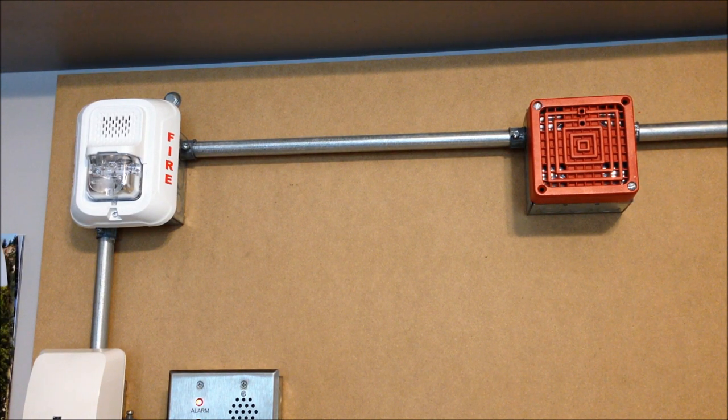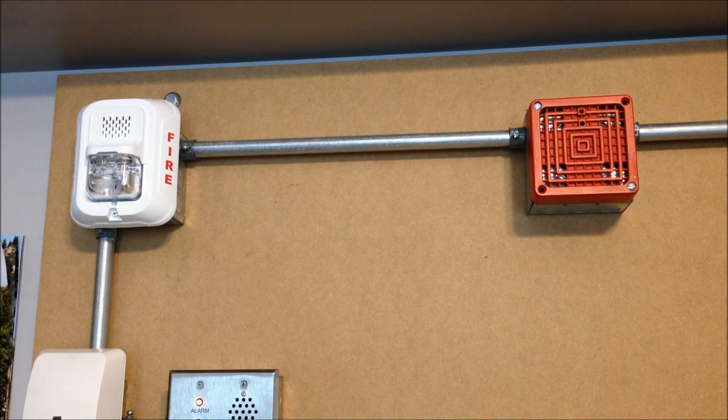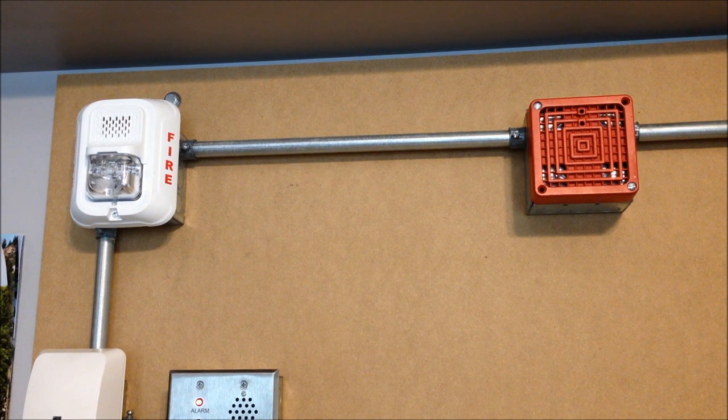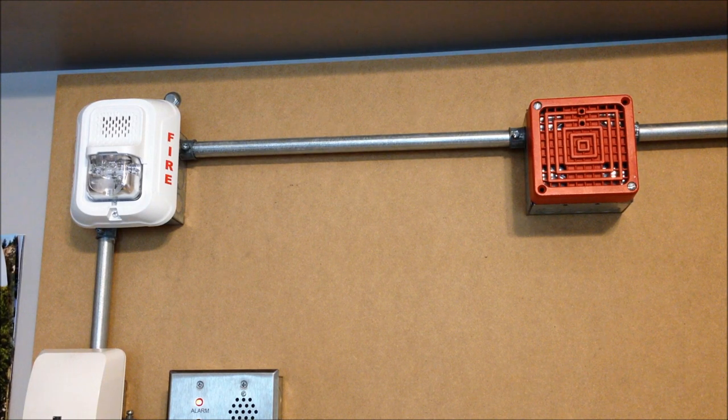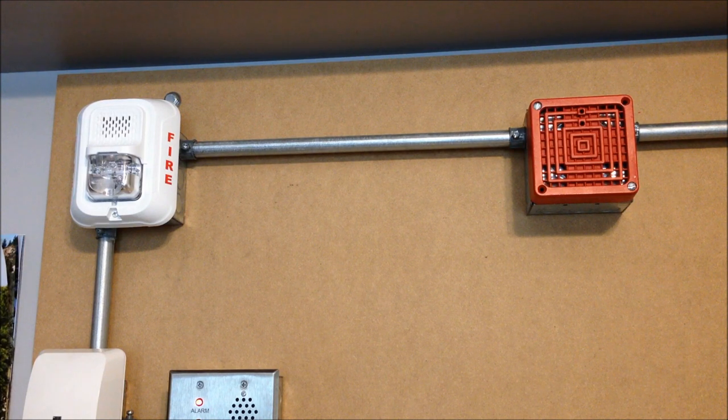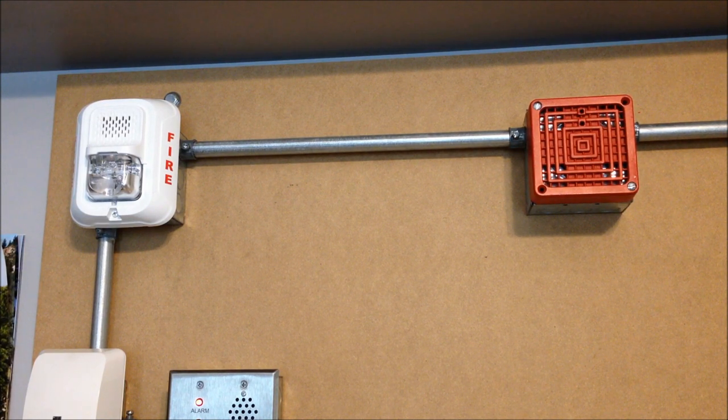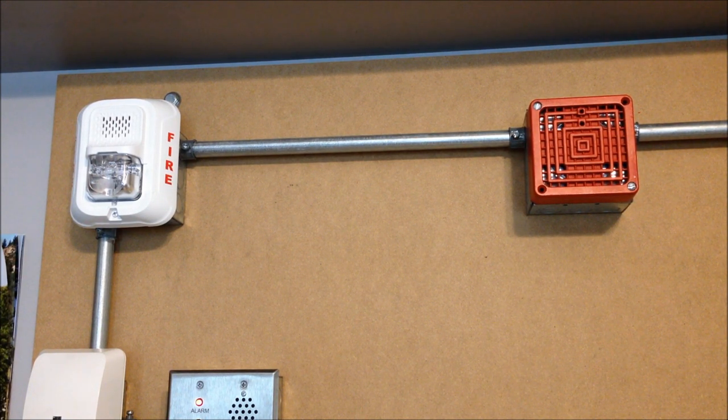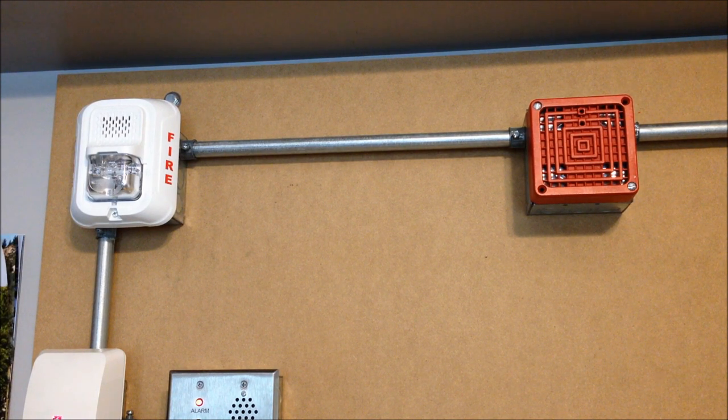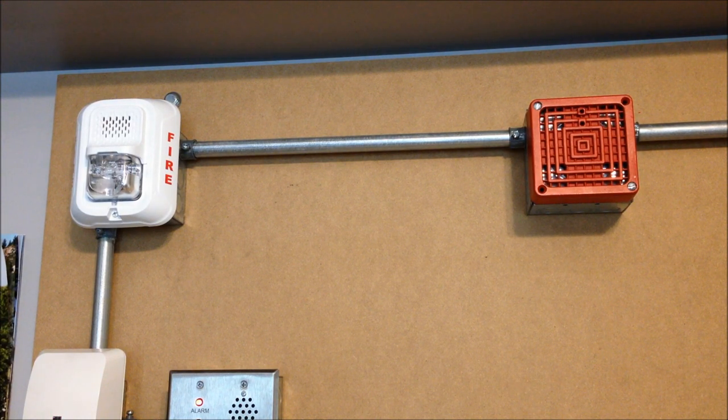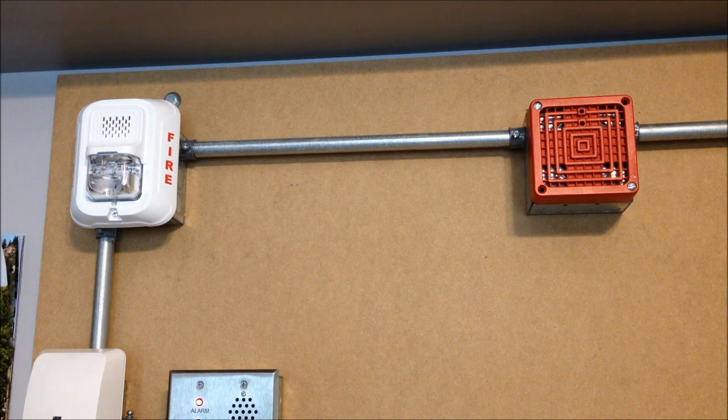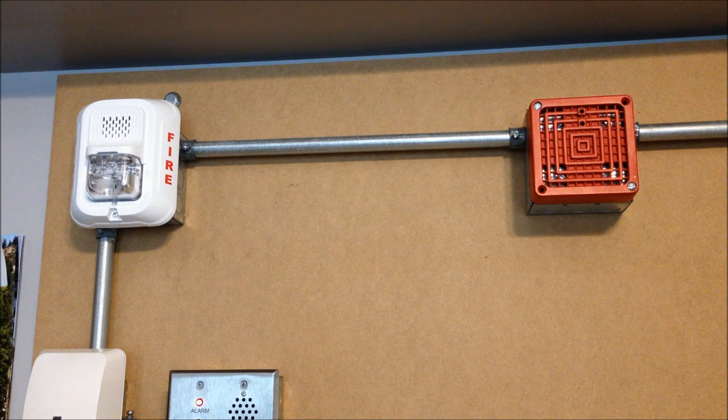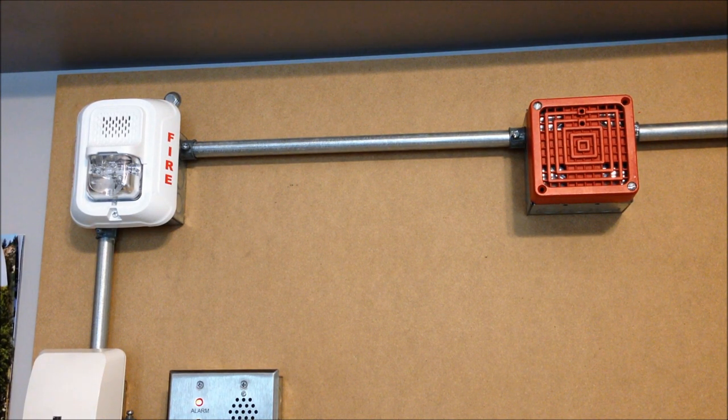We have a brand new System Sensor L-Series P2RL over there on the left hand side. It's the white version with the multi-candela strobe and it's going to be coding itself to code three on the highest volume. Over on the other notification appliance box we have a Federal Signal 450D Series C2. This is a little bit more modern of a mechanical horn. Obviously it doesn't have too much of a volume or coding adjustment on it, but it's going to be coded from the panel to code three to match up with the L-Series.